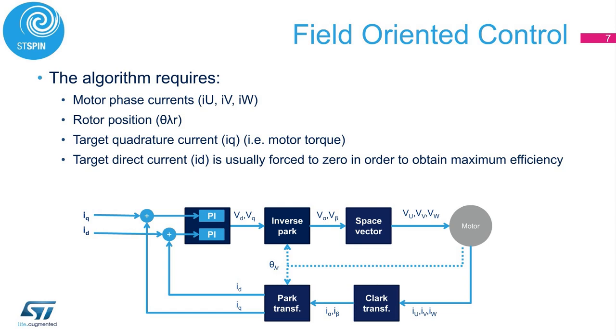The target quadrature current value is usually imposed by a second control loop according to the specific application. The most common control type is speed control, where the torque is adjusted in order to obtain the desired rotation speed. The last parameter is the direct current, but its value is usually imposed to zero in order to obtain the maximum efficiency. Negative values of direct current can be used to reach very high speed thanks to field weakening. However, this technique will not be explored during this presentation.